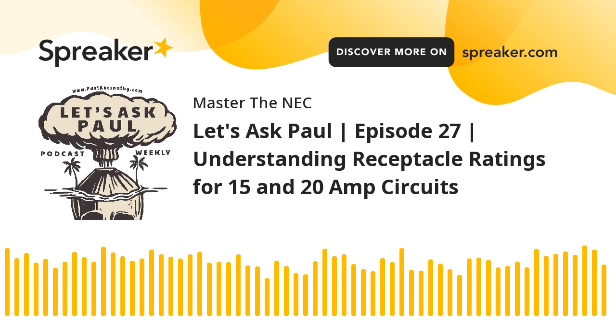So now we're going to jump up to a 20 amp rated overcurrent protected device, in our case, circuit breaker. So on a 20 amp rated circuit breaker, can I run 12 gauge out and put it on a 15 amp rated receptacle? The answer is yes, I can. I most certainly can do that. Table 210.21(B)(3) tells me I can. So then the next question is, well, obviously I can put a 20 amp rated receptacle on a 20 amp circuit breaker as well, right?